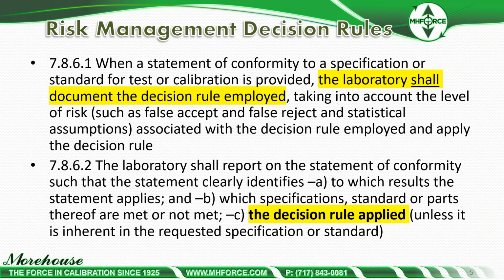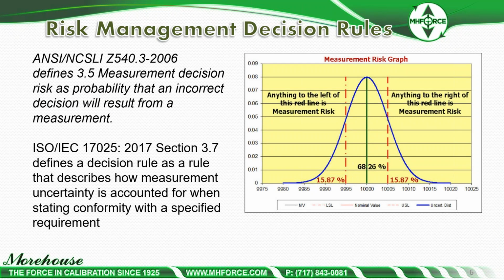And then 7.8.6.2 again talks about the decision rule applied unless it is requested specifically or in the standard. So if somebody says, hey, I want you to calibrate in accordance with E74, we just follow the standard. If somebody says, I want you to calibrate this device with a tolerance of 0.5%, we start asking about decision rules, ask questions. If you can do simple acceptance, you can do method 5, method 6. There are some rules that you can't do because you just don't have enough information.